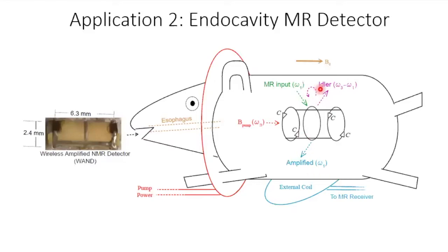So in order to realize this goal, we have to build cylindrical detectors that are easier to insert. So in this diagram, I have shown one example of a cylindrical detector that can work similarly to an implantable detector. This cylindrical detector has two identical vertical legs that are interlaced by end rings. Each end ring has a pair of varactor diodes aligned in a head-to-tail configuration. So once we turn on the pumping field on the actively oriented pumping coil, the pumping field will modulate the capacitance of the diodes on the end ring, in order to achieve efficient energy transfer from the pumping field to the MR signal. And then the MR signal will be received by the external receiver.